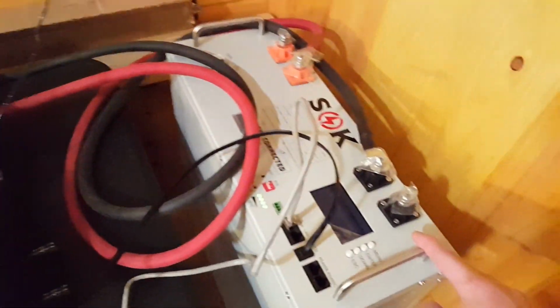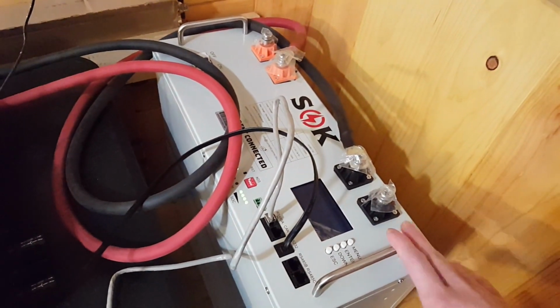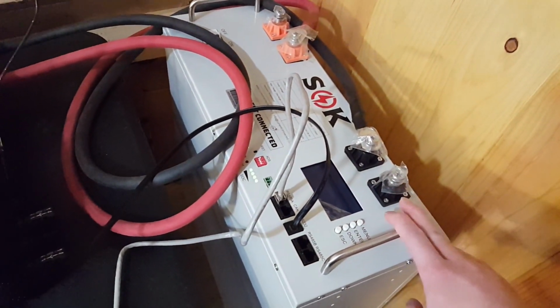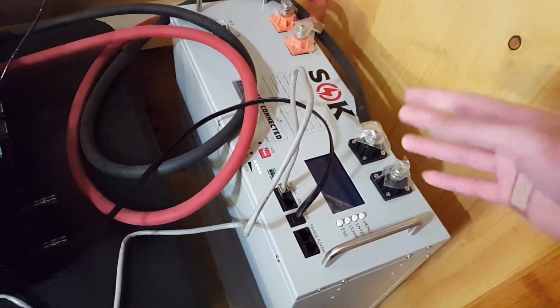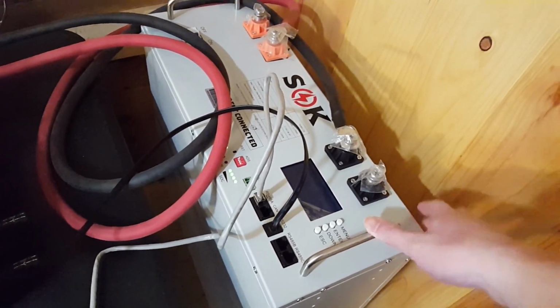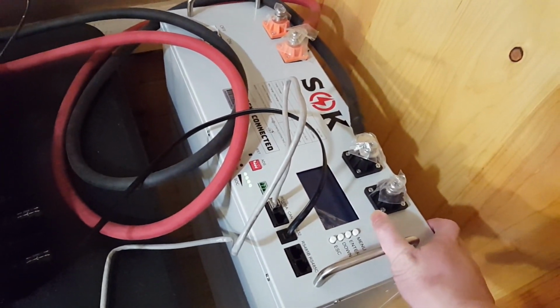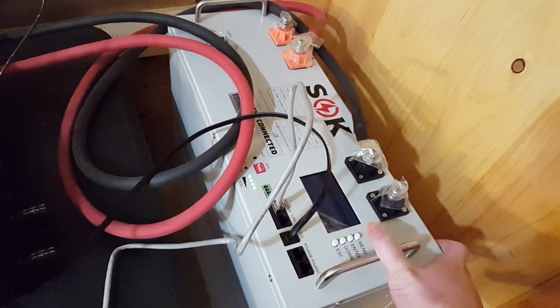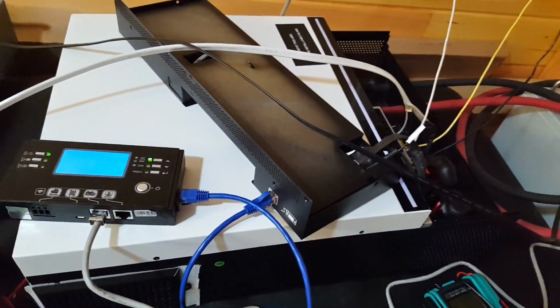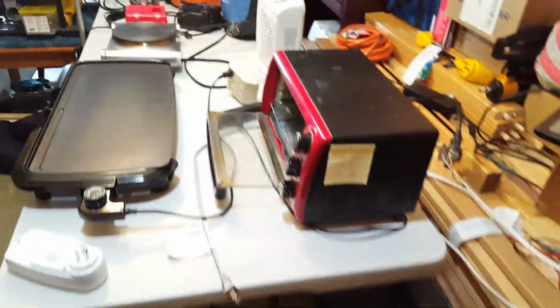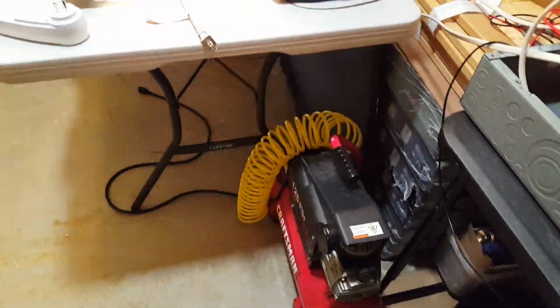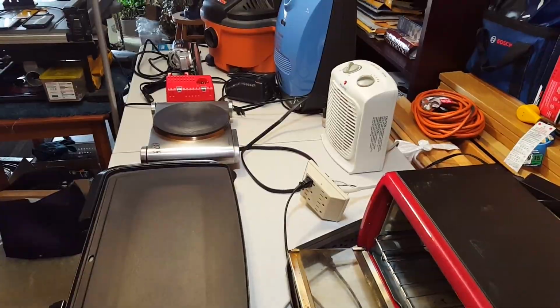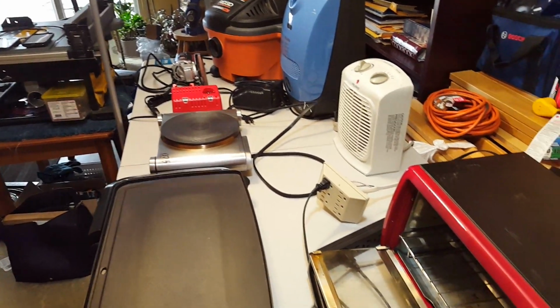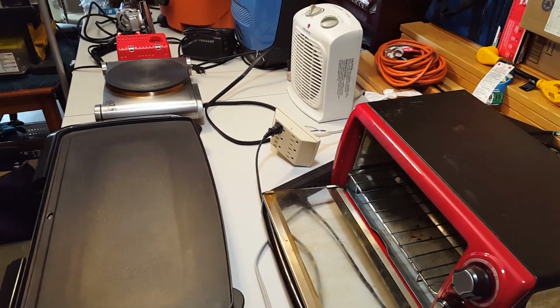I already know this battery here is supposed to be capable of doing 100 amps continuous discharge at the battery voltage. So given if it's 50 volts under a load, 100 amps, we're talking 5,000 watts of output power. And after inverter efficiency losses, we're looking at less than that. So all this stuff combined is going to be more than 5,000 watts. On the top left, there's also a table saw. We'll be doing some surge testing with the motors as well.